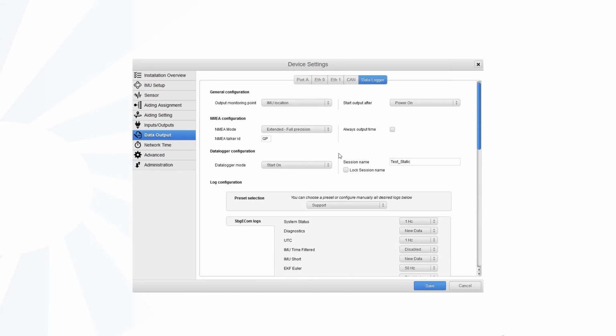In data logger configuration, there is a mode for resume state. Start off will disable the data logger at power up, and you can enable or disable it manually. Start on will enable the data logger at power up, and you can enable or disable it manually. In resume state, the data logger on or off state is kept from the previous power cycle, and you can enable or disable it manually. And finally, black box is a permanent logging mode that overwrites very old logs when the disk is full. In preset selection, support is ideal for post-processing and troubleshooting, so we recommend to select it.